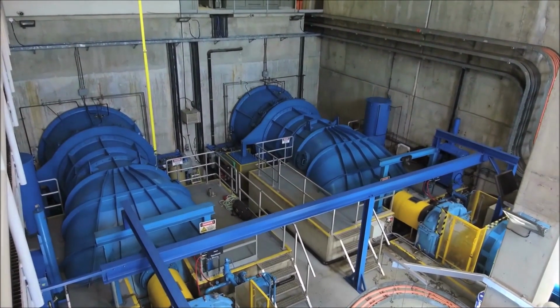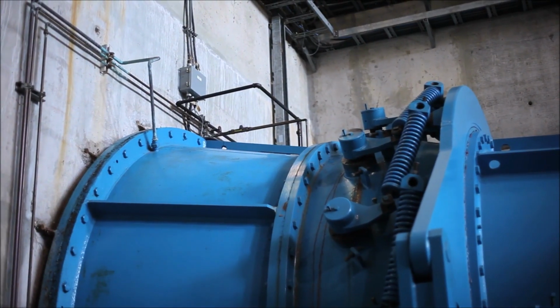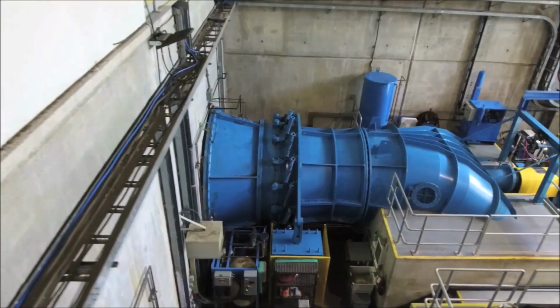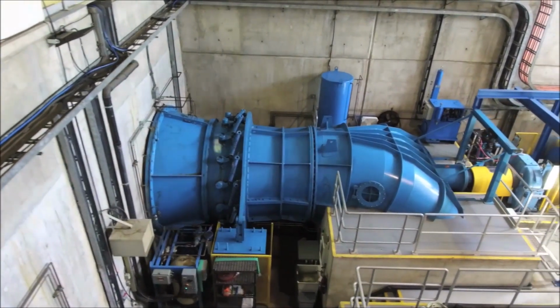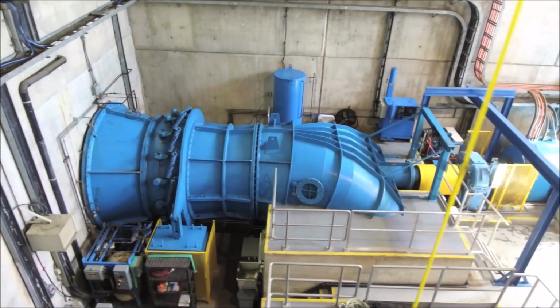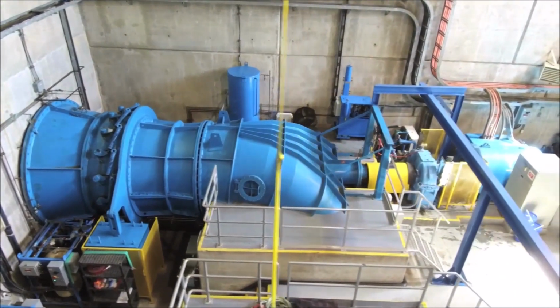These turbines are double regulated, first by wicket gates and then by controlling the pitch of the blades. This allows much greater control of the turbines to achieve the correct speed and thus contributes to the greater efficiency of the Kaplan design.